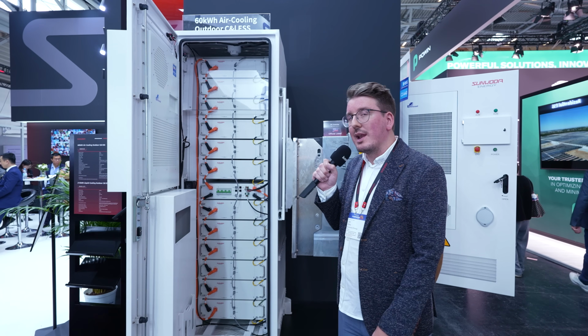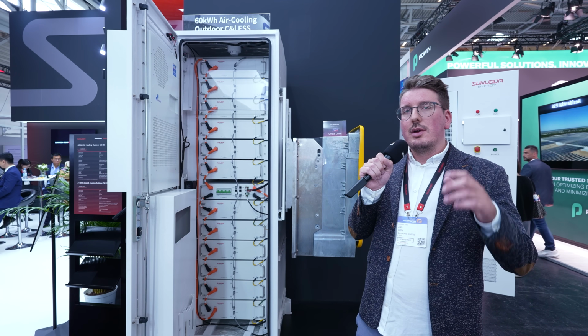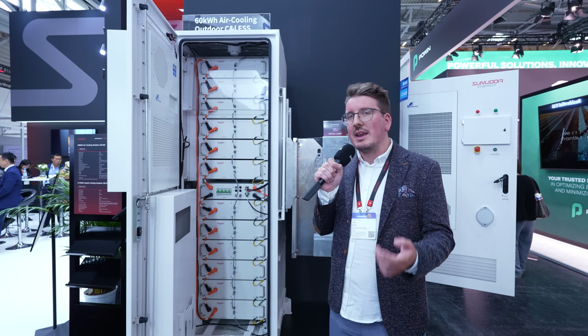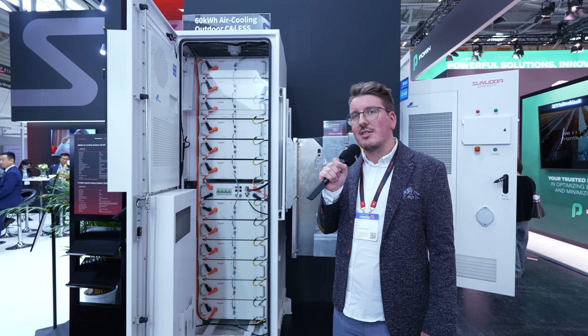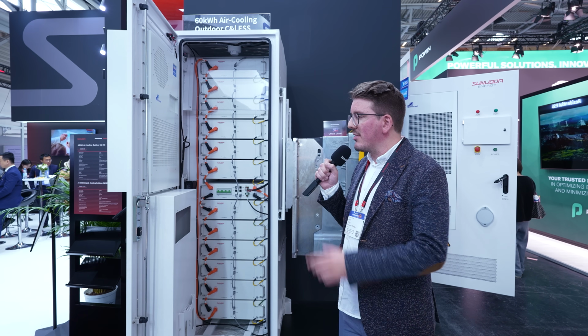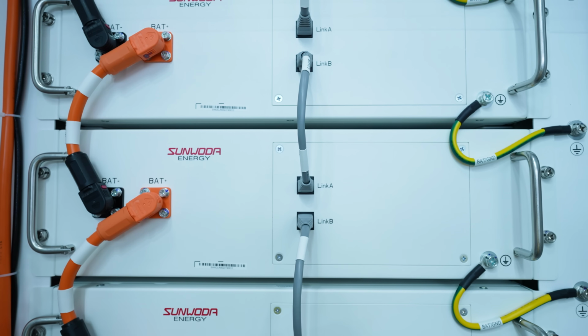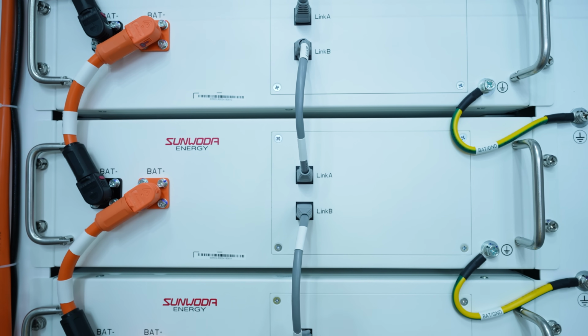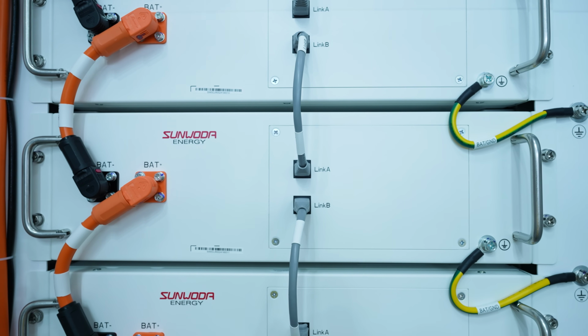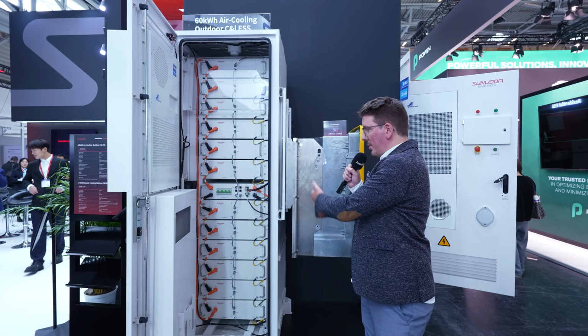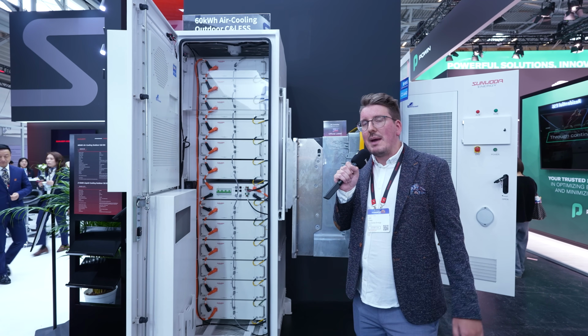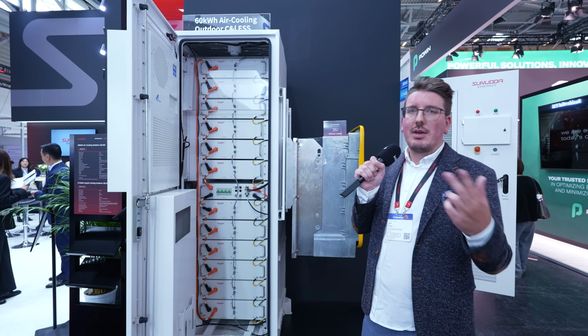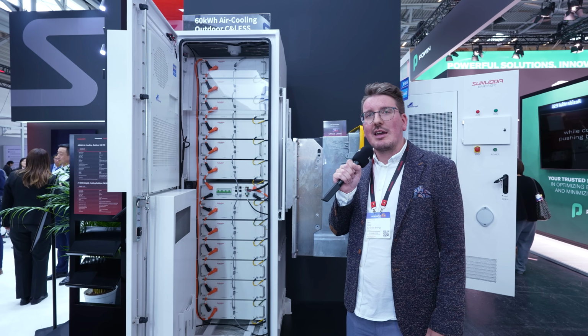This system is really flexible, from 1 cabinet up to 6 cabinets for 360 kilowatt hours. The system is plug-and-play for installation - really easy. We need only 3 cables from the inverter to the battery: plus, minus, and the communication cable.